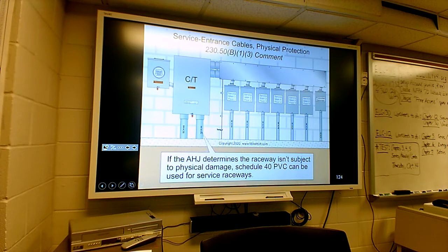Here, your inspector or your authority having jurisdiction, that will be the local electrical inspector. If the inspector determines that the raceway is not subject to physical damage, then Schedule 40 PVC can be used. I got Schedule 40 in here, but the way to clear yourself from having to do a job twice would be, when you plan a job, you want to jot down the materials you're going to use, Schedule 40 this or whatever. And when you go to actually buy the permit, or whoever goes to buy the permit from the inspector, show them your plans and say, I want to do this job here.